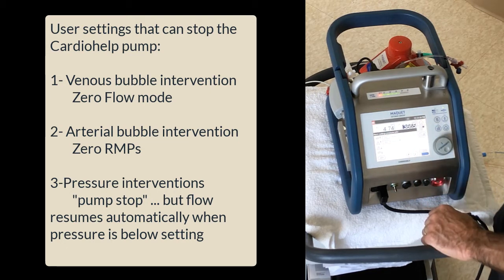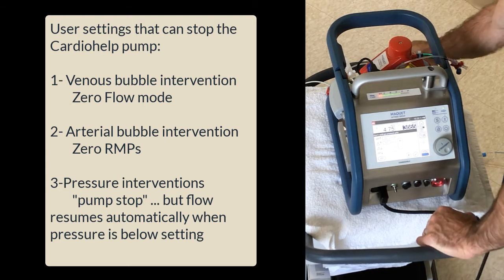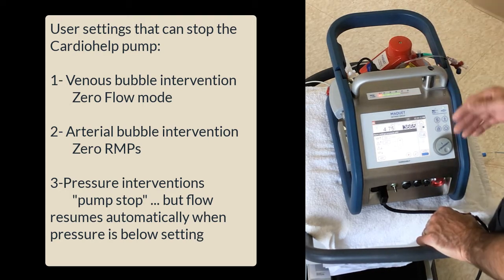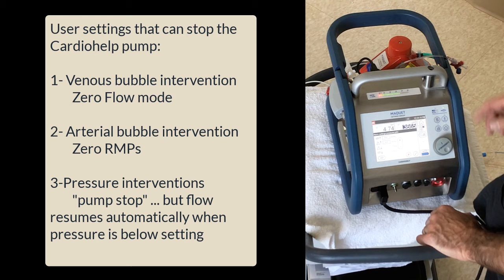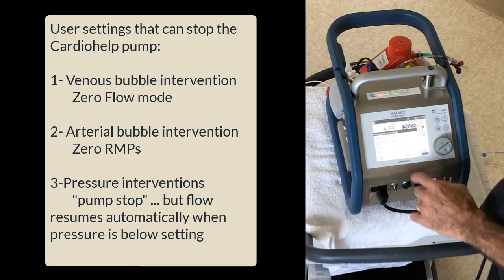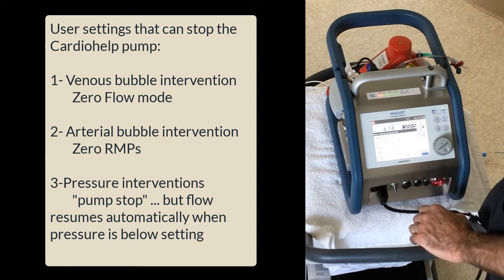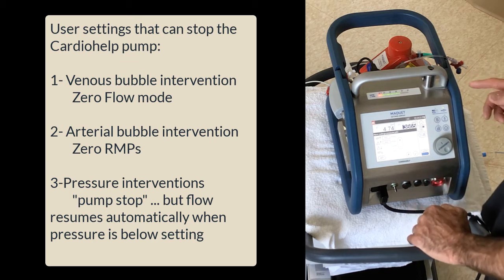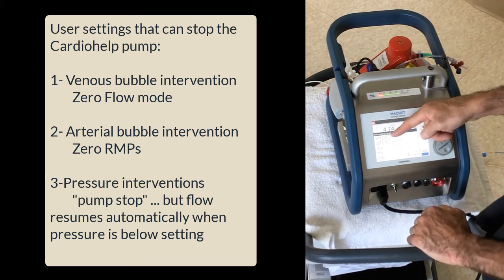Now, with an air bubble on the venous side, if it sees a bubble, it turns off the pump, and it's not coming back on until you tell it to come back on. With pressures, on the other hand, the pump has permission to increase the flow again anytime the pressure is below that top limit.